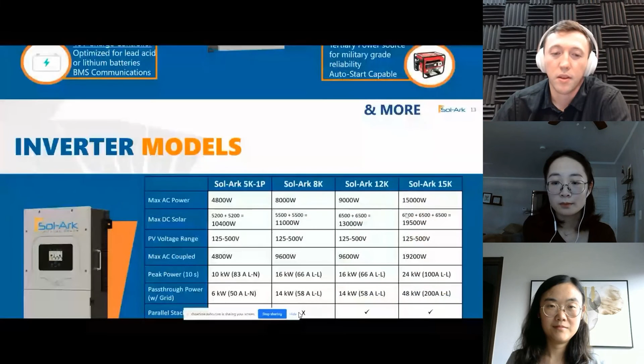Just a quick touch on our inverter models right here. We have our 5K single phase, our 8K, our 12K, and our 15K. You're going to see here across the board, each one's going to have a different AC output value and a different amount of DC solar tied into the MPPTs. The PV range is going to be the same, up to a 500 volt string in series into each inverter. If you would like to AC couple into our products, you will be able to do so as well.